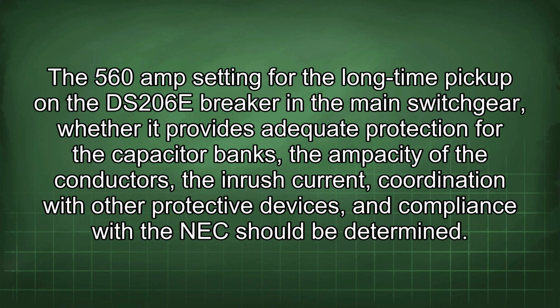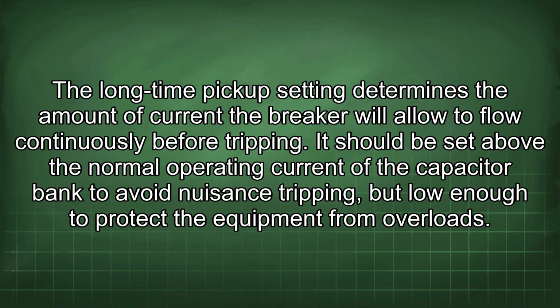The 560 amp setting for the long-time pickup on the DS206E breaker in the main switchgear, whether it provides adequate protection for the capacitor banks, the ampacity of the conductors, the inrush current, coordination with other protective devices, and compliance with the NEC should be determined. The long-time pickup setting determines the amount of current the breaker will allow to flow continuously before tripping. It should be set above the normal operating current of the capacitor bank to avoid nuisance tripping, but low enough to protect the equipment from overloads.